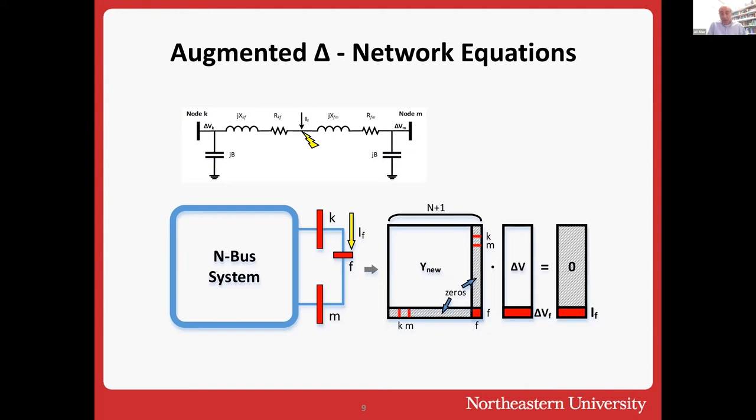And here we are also doing a difference equation. Instead of just writing the equation after the fault, we are writing the equation in such a way that we subtract the post-fault network equations from the pre-fault network equations. So as a result, you will see that we are calling this vector now delta V, indicating that this is the difference between the post-fault values minus the pre-fault values at each of those buses. And assuming that this fault occurs all of a sudden, we approximate the changes in the net injected currents at every bus with zero, because typically loads and generation don't really change that fast instantaneously. The only change we expect, of course, is this fault current, which is the reason why the system has changed.